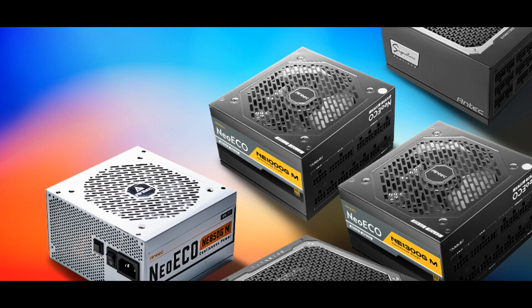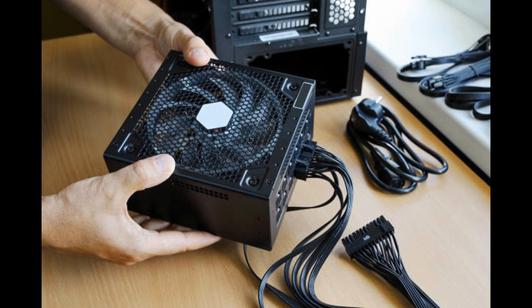Isolated power supplies are widely used in various industries and applications where safety, noise reduction, and system stability are critical. Below are some common applications. 1. Medical equipment - Safety: medical devices often require isolated power supplies to protect both the user and the patient from electrical shocks. Isolation helps meet stringent safety standards like IEC 60601. Examples: patient monitors, defibrillators, imaging systems (e.g., MRI, CT scanners), and diagnostic equipment.